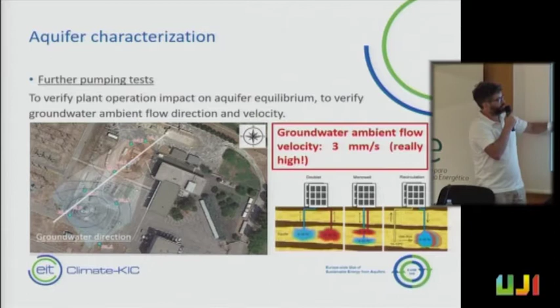Another important thing is that we were able to measure the groundwater ambient flow velocity, which turned out to be really high, probably due to the thin layer of aquifer. For the conditions of this specific site, we have a really high velocity, and that's why we decided to use this approach, quite different from the one used in the Netherlands, where you have a sort of static aquifer. There you can use a cold well and a warm well instead of extraction and reinjection, because depending on the season you can reverse their functioning. In these conditions, though, it's better to use this kind of strategy: you always extract water from these wells and inject the water in this one.